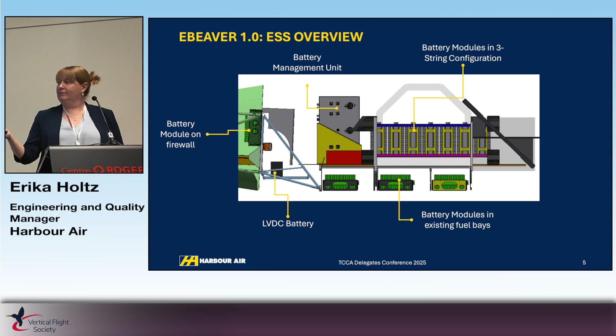In version 1.5, we took those modules out and installed a completely new system. These modules are quite a bit lighter, but still heavy. We did gain a little energy density in these. This time we went to a 4-string system, and each string fed an inverter.